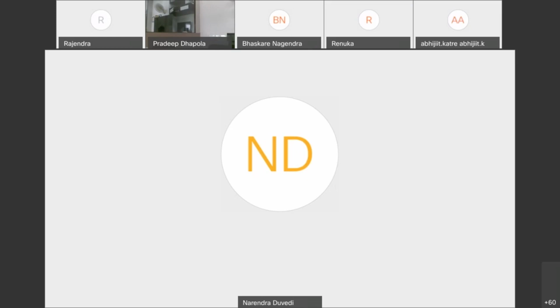Presently, what is happening is MSCDCL, although it is written in their own supply code, their field staff is not aware of what the standard says. Rather, this is happening everywhere in the country. Why only MSCDCL? They just come for some time, measure your harmonic distortion, THD, not even TDD, and based on that, they say whether your distortion is more or less. So as far as compliance is concerned, a slightly complicated measurement and calculation is required, which we normally do when we conduct audits. Yeah. Details about harmonic compliance and solutions would be a totally separate webinar, which can be conducted for a similar period.